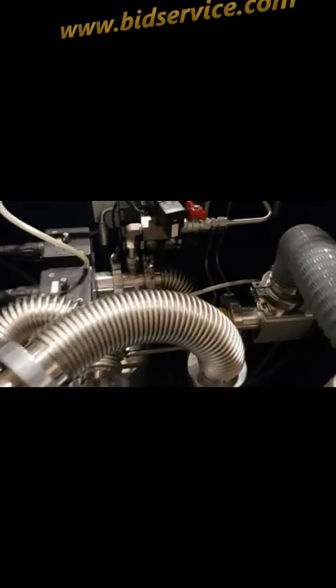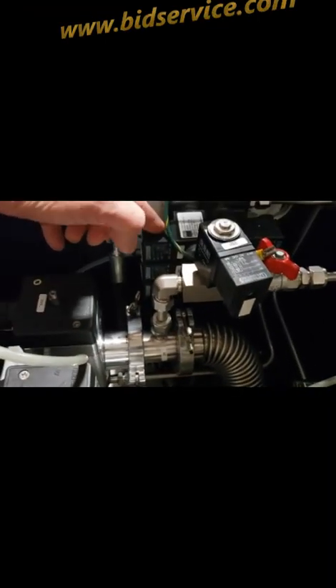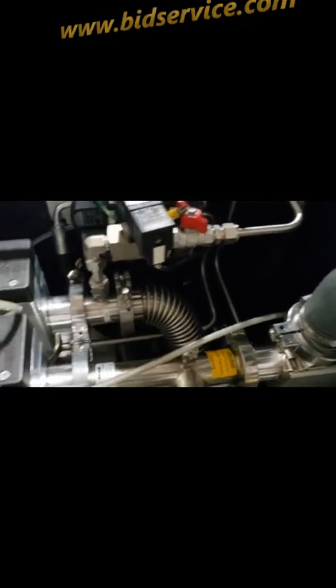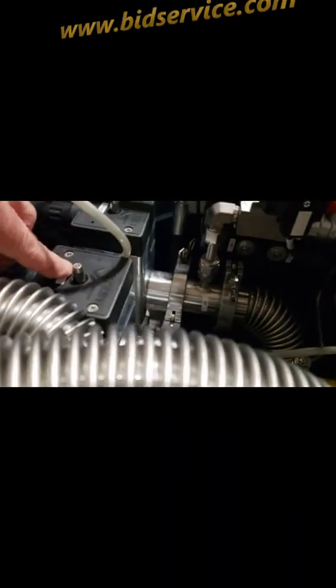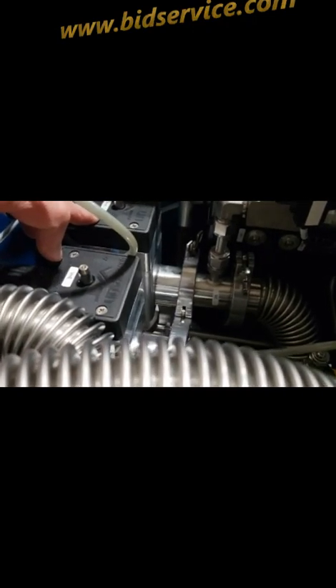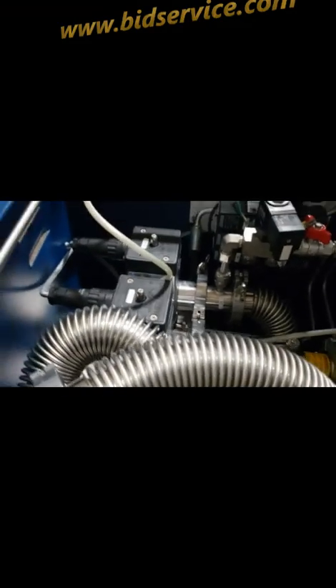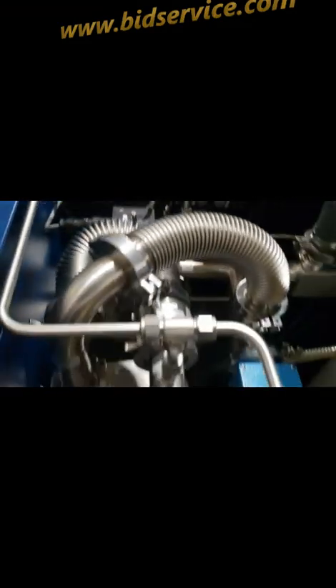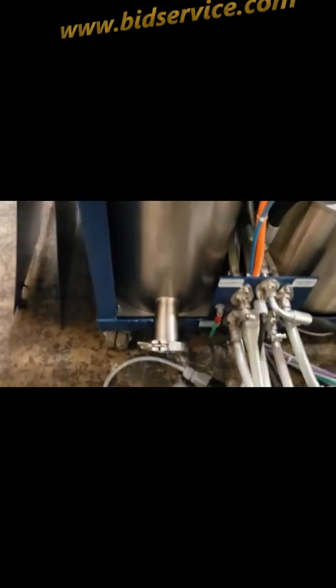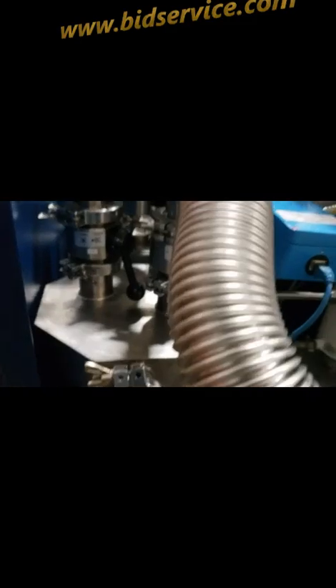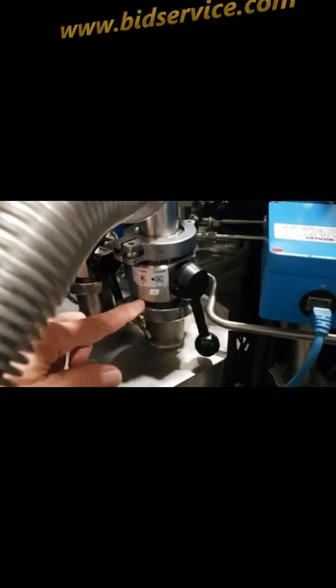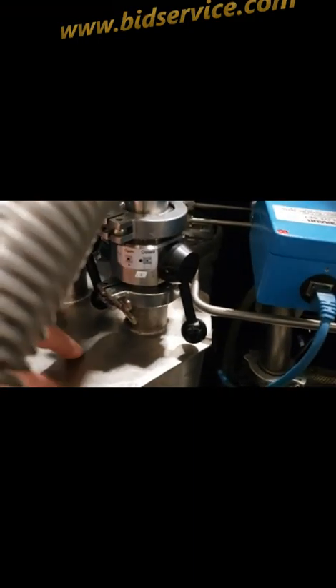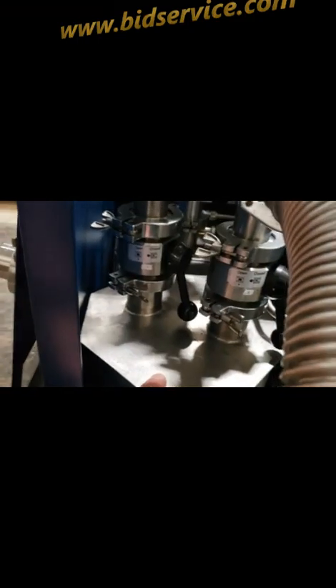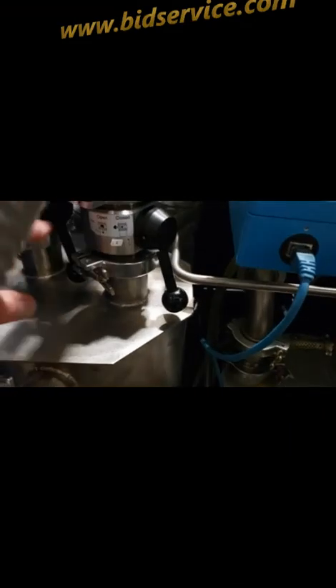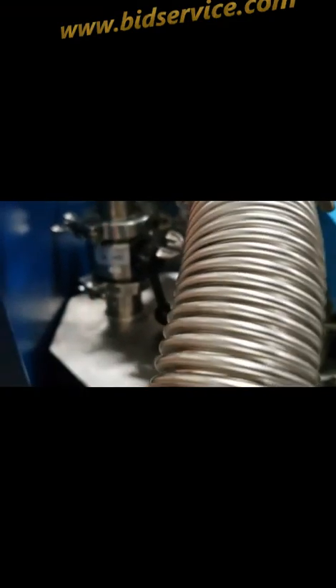Point out real quick, you do have your valve manifold here, the control valve. Down in here is your purifier. These two valves here will isolate it when closed. The media has been replaced and regenerated. There is a solvent trap here. These two valves here are open to allow the flow of gas through the carbon media. That has been replaced too. So it'll come in here and then out here. If you decide you don't need it or you need to replace it, you can close these two ball valves and open the bypass valve, which is right here.